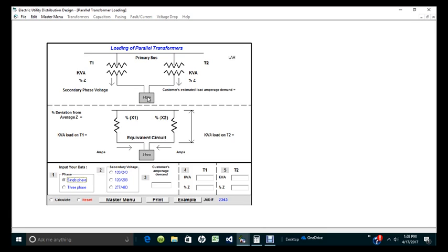It could actually go directly from the transformers to the underground pull section in the service panels itself. So either way, you'll have the same number, whether you're terminating at a junction box and then going from the junction box with parallel runs directly to the panel, or you're coming directly from the transformer, each transformer going directly to the panel without using the junction box. The value is still going to be the same.